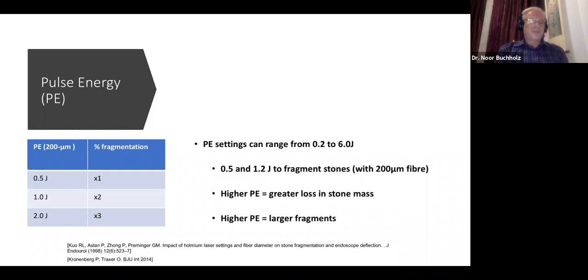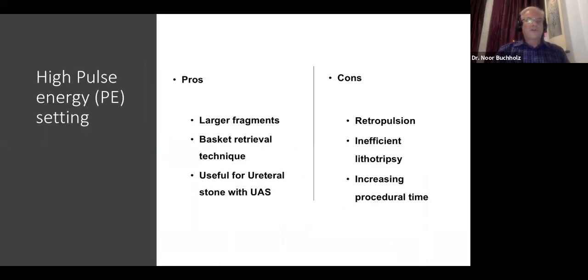Now on the left side, you see this table. It does show that fragmentation is increased with energy. There is no doubt about that. You get a greater loss in stone mass over time. But when you ramp up your energy, you get larger fragments as well. So the pros of a higher energy setting is larger fragments.